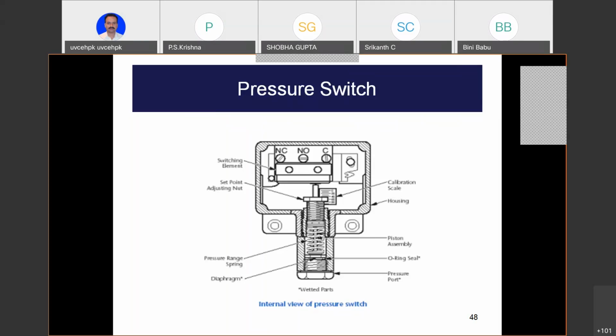So, I told 3 things in a very simple way. One is a fault or failure, a safe failure. It was an unnecessary trip of the plant, but it cost your company money. The second one is a silent killer. You don't even know that the pressure has reached such a high state and the switch is sleeping. And no way you know, and it has spoiled the entire area. The other one is a healthy one. That is, actually the pressure went high, it's tripped. So what is this? This failure is called failure to danger, failure to safety.